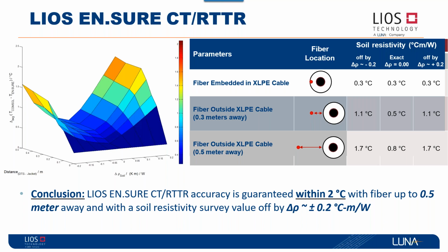This is very, very important, because the main point here is the accuracy of the DTS measurement. So, a good instrument. The second thing is that what you really need is a strong engine that can leverage the fiber optic technology by looking at the temperature of no longer the fiber, but the ability to start looking at the conductor temperature for each one of those circuits.